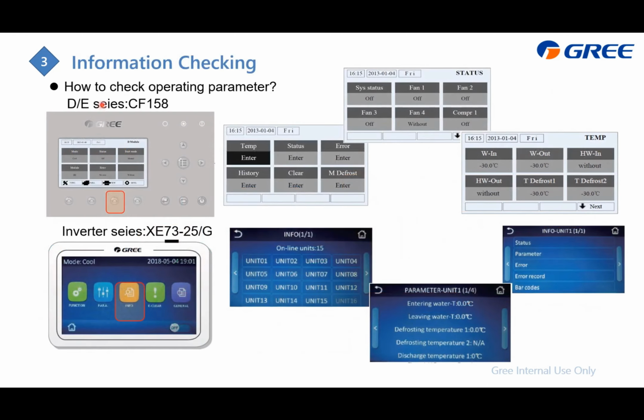As for how to check the operating parameter, for the on-off, which is the D or E series, which use this CF158 controller, just press here to check and then select which out unit, which is which chiller, and then select the item, either the temperature or the component status. So here the status will display the status of the components, and here is the temperature.